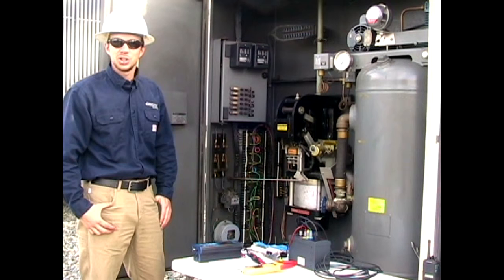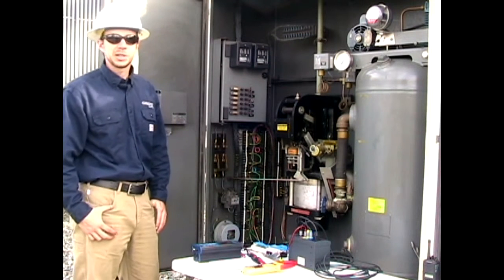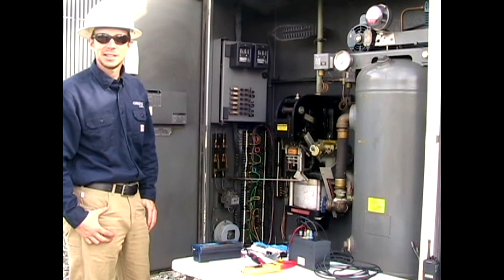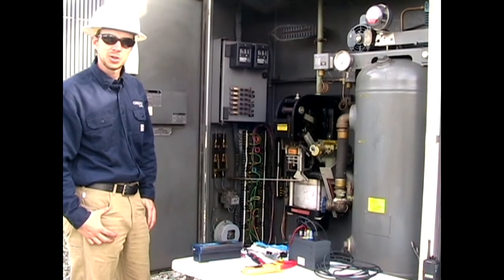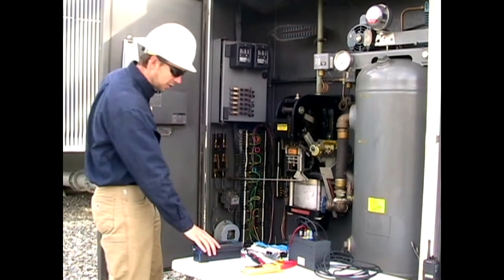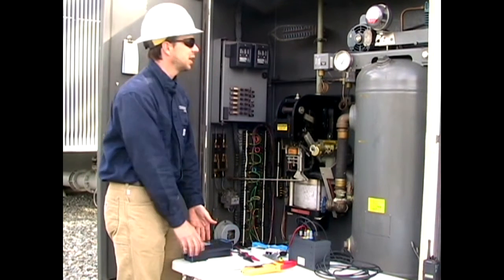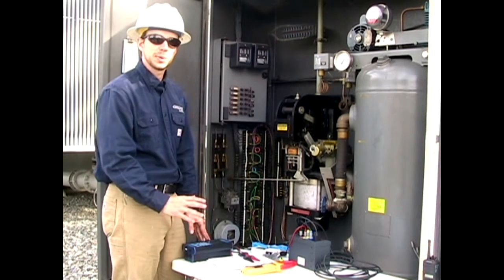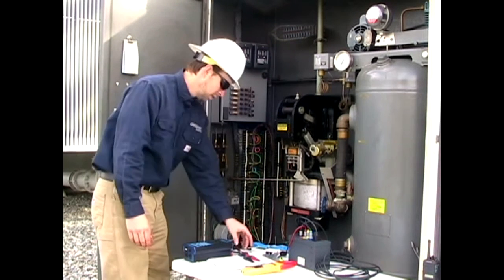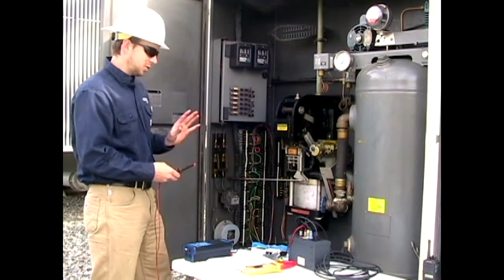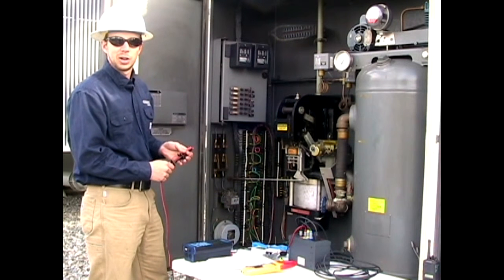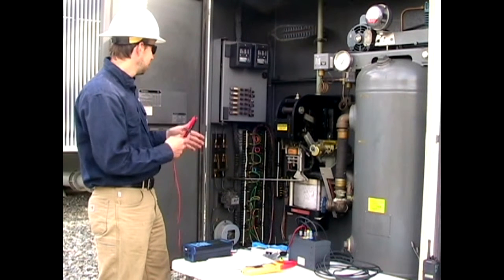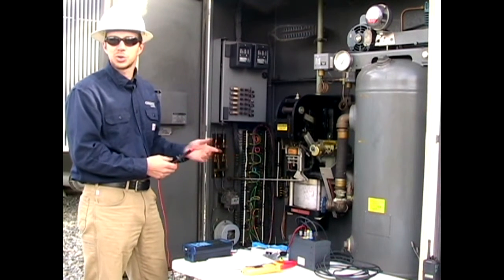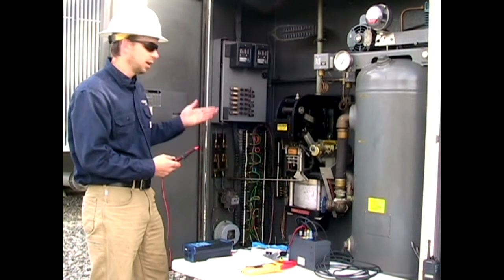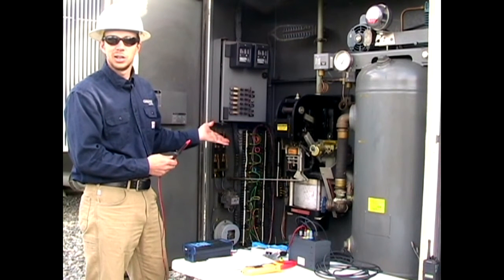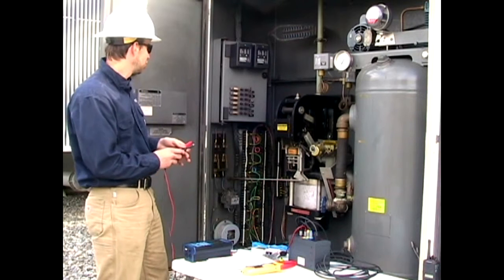We're here at International Substation with a Westinghouse AA10 breaker, and we're going to catch the first trip using the Kelvatech profile tube. And this is an energized breaker, and it is in the closed position, so we're going to catch a trip. So before you start to catch a trip on a breaker, you probably need to go through the prints and verify where your wires lead to your closed coil, where your wires lead to your trip coil, and then which CTs are in use, so you can use them on your trip.